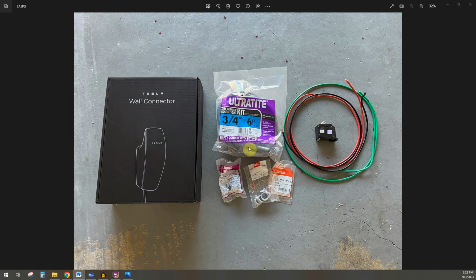You can use basically whatever conduit you want, I think. That includes metal flex conduit, PVC conduit, or EMT, which is the metal conduit that you normally see on the outside of houses. So any conduit is fine. Make sure that your THHN is inside conduit. If you're using Romex inside the wall, you don't need conduit because it's sheathed. So that's the protection for the insulation on the wiring. But again, I'm using THHN, so I need conduit.